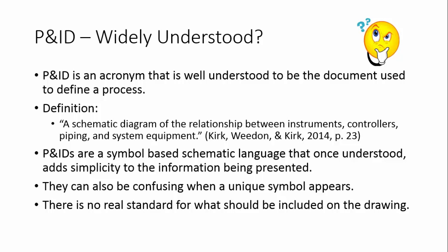Because there is no standard, this can cause a lot of confusion when a technician or an engineer is trying to decipher the meaning of a unique symbol that a designer or another technician included on a P&ID. It's good practice that if you're going to use a custom symbol or a unique symbol that doesn't appear in any standards or any type of documentation book, that on the P&ID you include a note or a key that shows you the symbol and what it is that that symbol is representing.